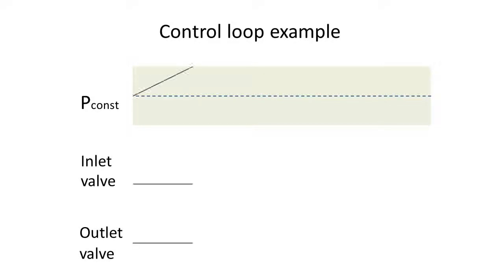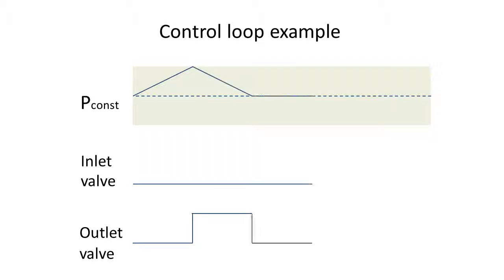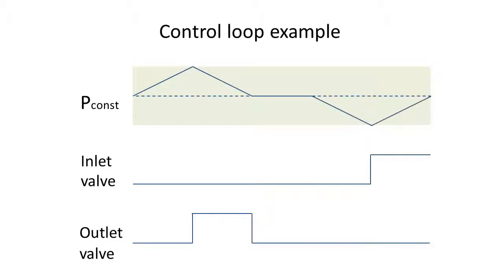Assume the pressure is increasing. When reaching the tolerance band, we open the outlet valve. The pressure normalizes again. Leakage causes loss of pressure. We have to open the inlet valve and activate the pump.